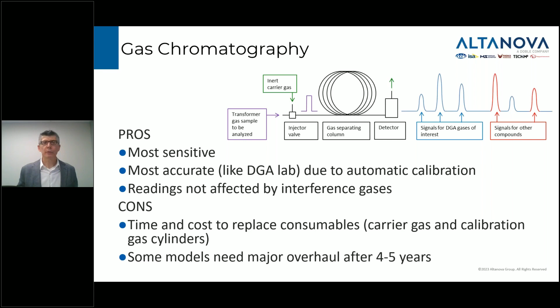The big downside, of course, is that in order to run a gas chromatography monitor, we need a cylinder of helium gas and we need a cylinder of calibration gas. And there's cost and time associated with managing, changing out those cylinders every 4 years. And not everyone wants to do that. So that's one downside. And the other downside is that for some models that use gas chromatography, the gas separating column sort of wears out after a period of time, so they need a major overhaul after 4 or 5 years of service.